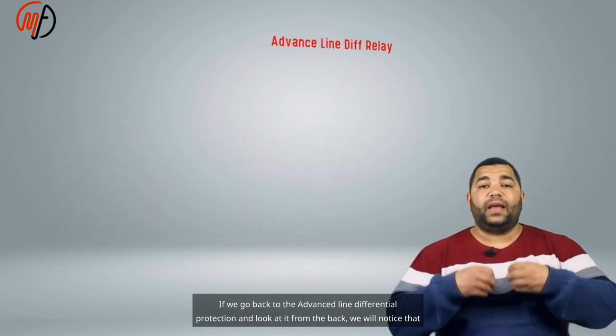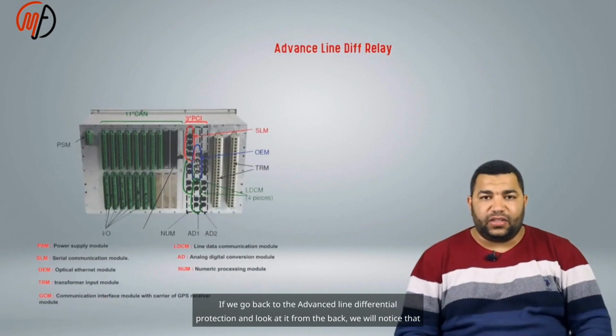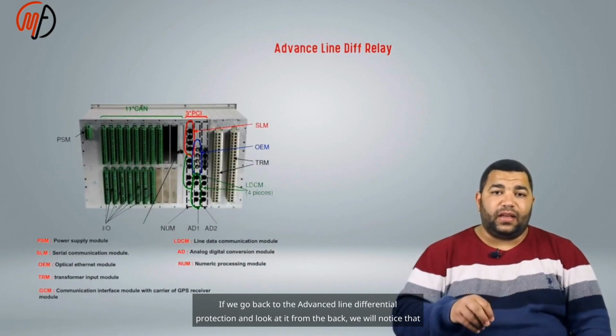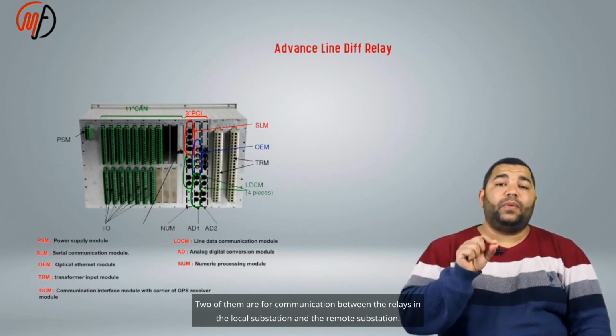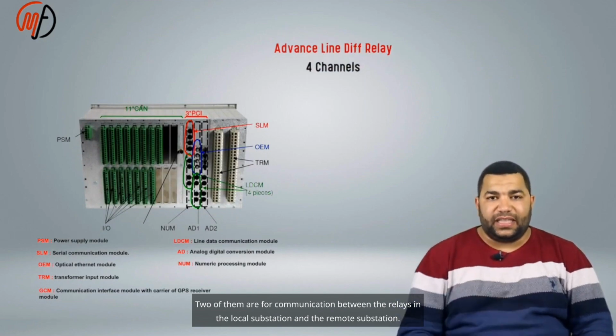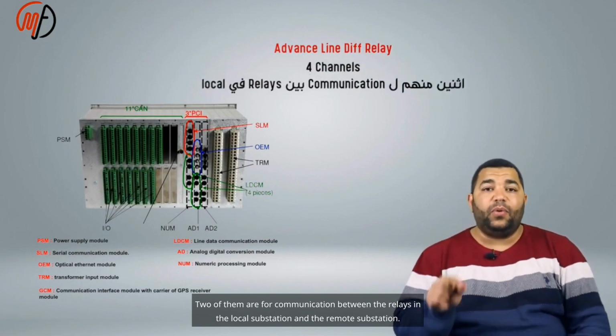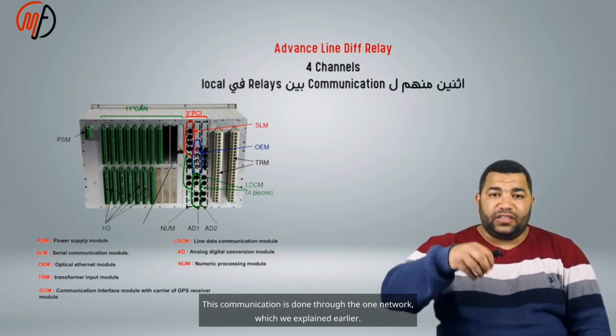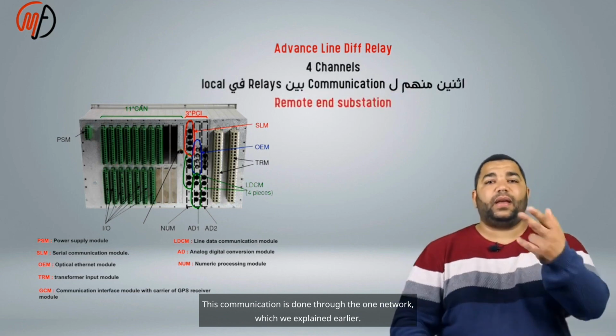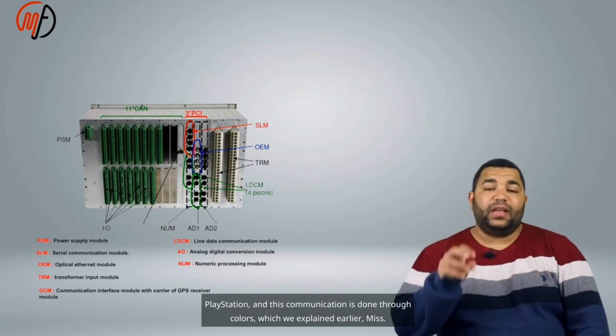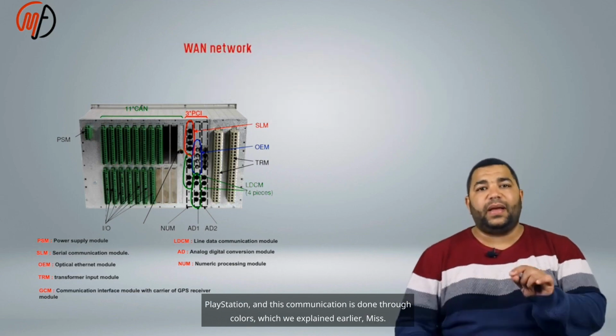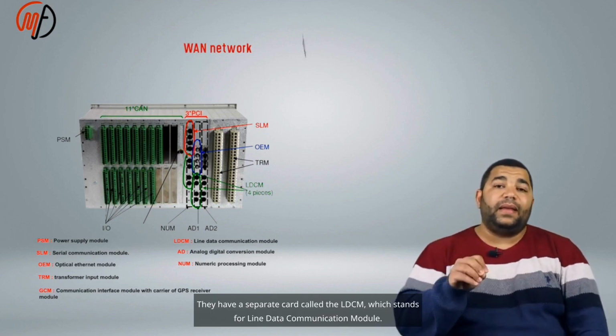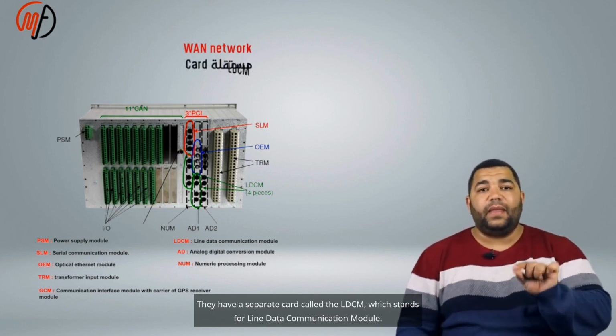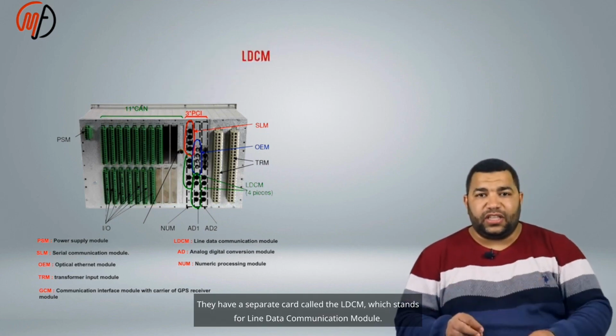If we go back to the advanced line differential protection and look at it from the back, we will notice that there are 4 communication channels. 2 of them are for communication between the relays in the local substation and the remote substation. This communication is done through the WAN network, which we explained earlier. They have a separate card called the LDCM, which stands for Line Data Communication Module.